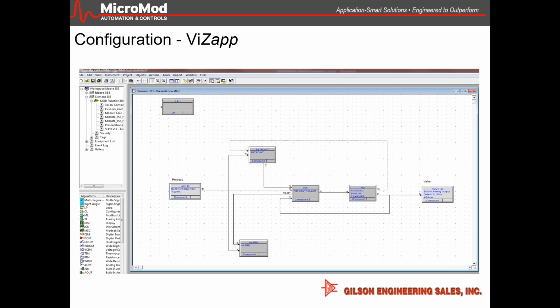This is where all your function codes and FCOs reside, and you're able to bring those down. In the same way, at the bottom left, that's the native programmer, so you can bring those in as well. Basically you bring a loop compound over, open it, place your IO in it, place the functions and algorithm you want, tie it to a configured list or a Modbus list or whatever it needs for communications, then save it and download it. It doesn't care if it's Bailey, Moore, Siemens, Mod, or Taylor. It really doesn't care.